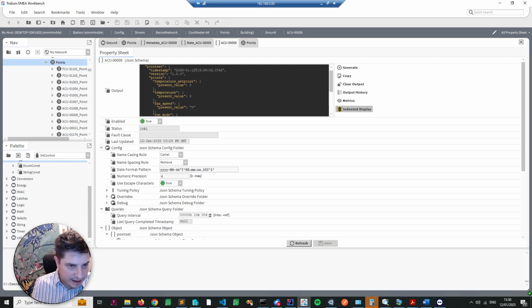So we have a point set envelope. Within that we have the timestamp. We have the UDMI version that it was created against, because the version of the UDMI is always developing going forward. So we need to be cautious that we put in the version of the UDMI that we delivered the project to at that time.